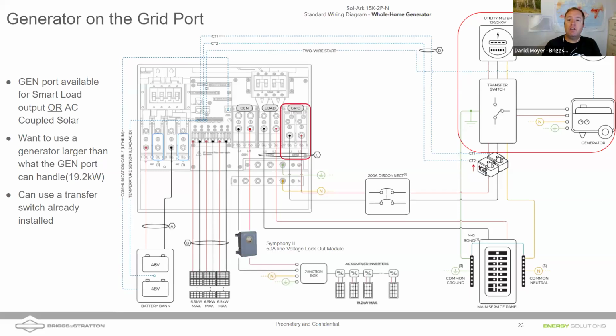So another thing that's been a big topic in the industry is AC coupled solar. We come out to a house, and this is, I think, a very powerful testament to how a Sol-Ark can be operated. You come out to somebody's house that has existing grid tied solar, and they maybe didn't realize that when the power goes out, their AC coupled solar goes out, right? That grid interactive inverter is looking for grid. If it doesn't see it, it's going to shut down. UL 1741. It's not going to want to backfeed the grid.